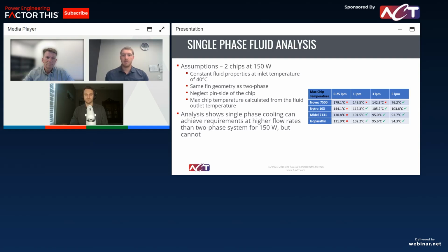and how much space claim you have for the evaporator. So you need to design the internal channels of your evaporator to do that cooling. So in terms of kilowatts or total power capacity, there's really no limit. But in terms of orientation and space claim, there are certain situations they can work in, but for the most part they can work in most situations.